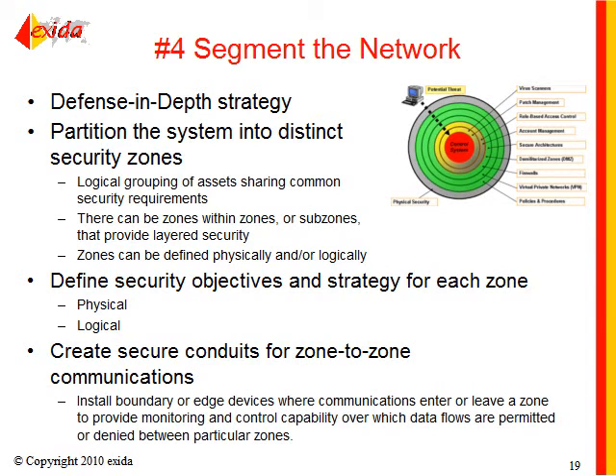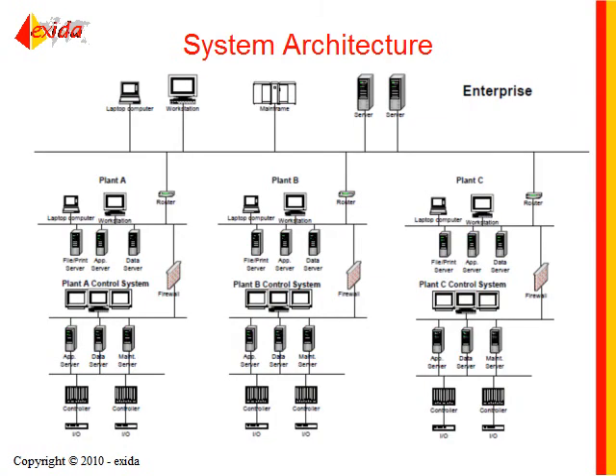By that we mean borrowing from the IT world, which has long been compartmentalizing networks. We need to partition our control system networks into distinct security zones. The idea of zones is to group together assets that share common security requirements. There can be zones within zones and subzones, and zones can be physical or logical or both. The key is to define the security objectives and strategy for each zone, then create secure means to communicate from zone to zone - we call those conduits.